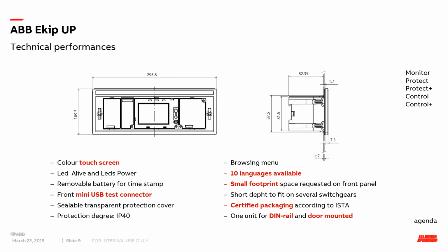There is a sealable protection cover too. Some of the sites that have a very tedious locking mechanism, or lock system, like to have red lock, yellow lock, blue lock in terms of their operation, such as oil and gas applications. You can utilize those lock activities quite easily in front of the relay and secure and seal the access to who can change settings or whatnot. Obviously, the settings are password protected, so you're able to change that password or provide those passwords. Protection degree is IP40.